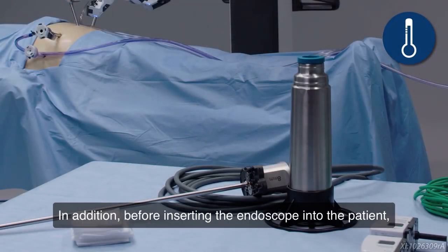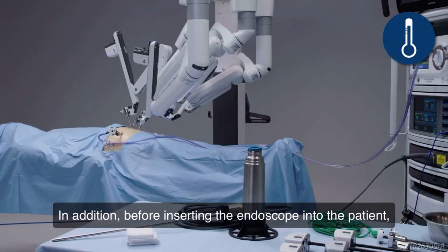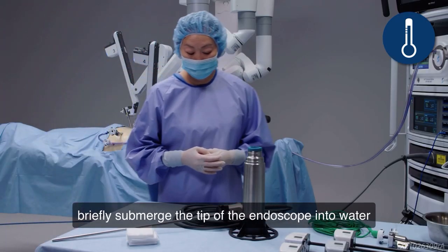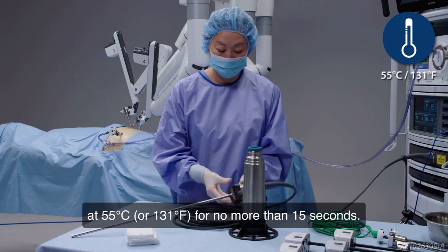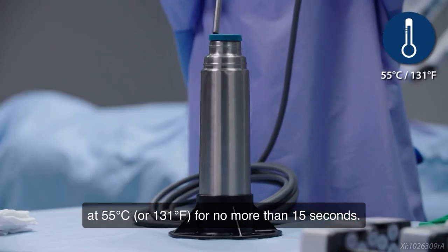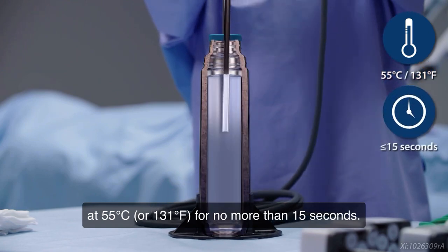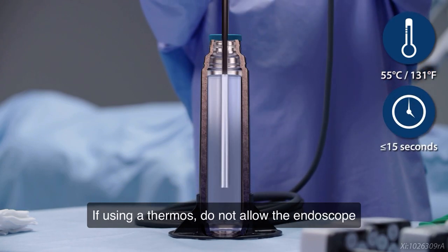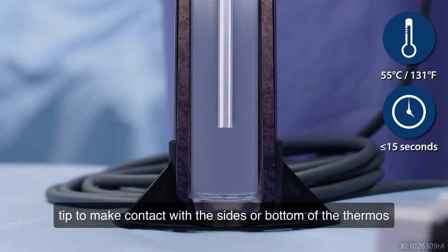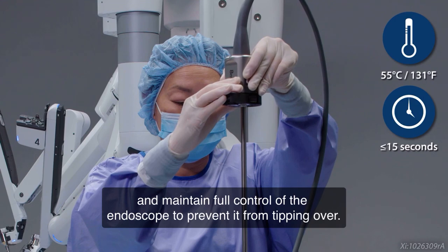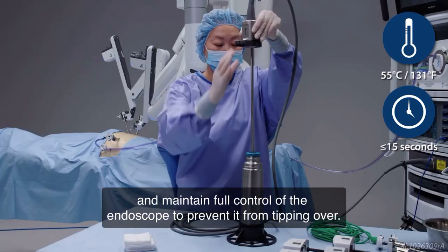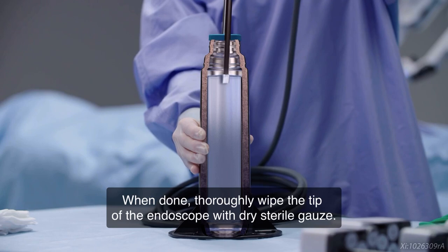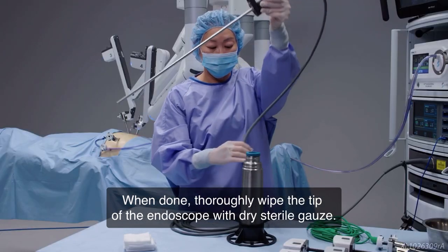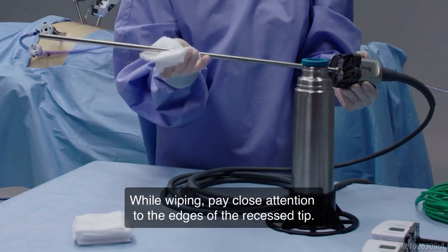In addition, before inserting the endoscope into the patient, briefly submerge the tip of the endoscope into water at 55 degrees Celsius or 131 degrees Fahrenheit for no more than 15 seconds. If using a thermos, do not allow the endoscope tip to make contact with the sides or bottom of the thermos, and maintain full control of the endoscope to prevent it from tipping over. When done, thoroughly wipe the tip of the endoscope with dry, sterile gauze. While wiping, pay close attention to the edges of the recessed tip.